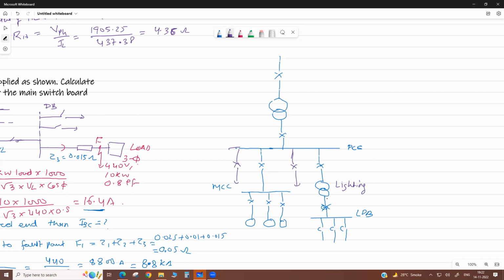Why do we isolate? Because in this lighting circuit our switching operations are frequent. We just switch on and off the PCs, lights, fans, heaters, like your appliances. Due to this switching operation there is voltage fluctuation in the main bus bar. Then your loads face the voltage fluctuation, and motor performance is affected. So this is the fault-prone zone. That's why we have to isolate this.